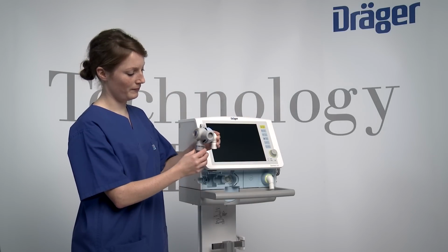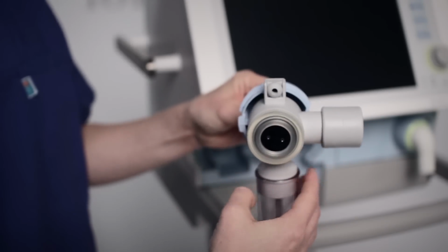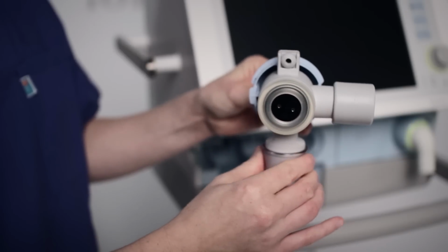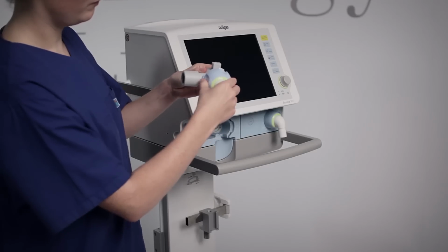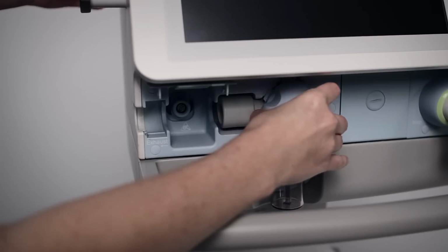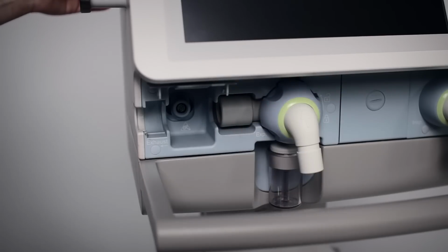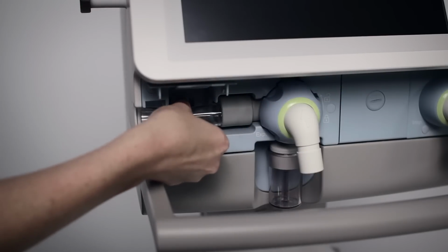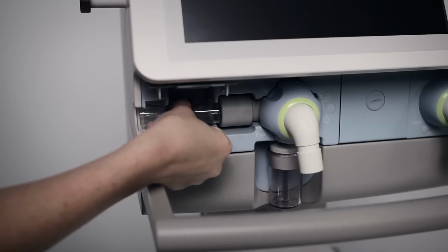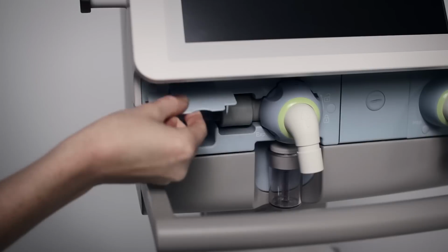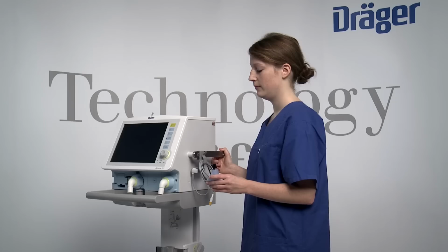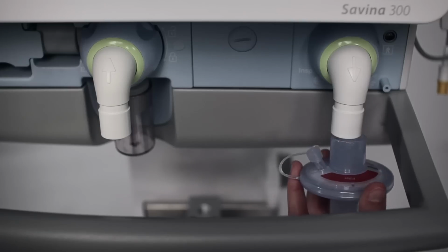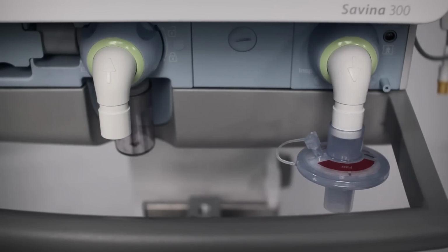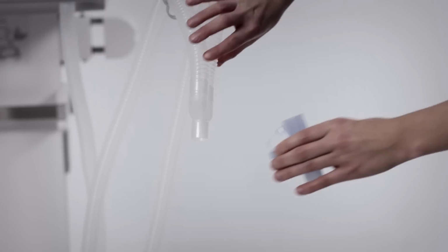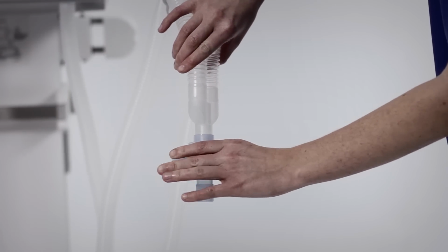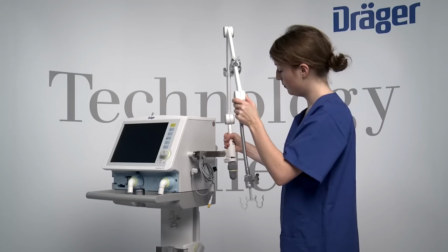Prepare the expiratory valve. Check that the diaphragm fits properly onto the edge of the expiratory valve housing, and that the flow sensor sleeve and the water trap container have been attached. Then insert the expiratory valve. After that, insert the flow sensor and push it up to the stop in the flow sensor sleeve of the expiratory valve. If no breathing gas humidifier is used, we recommend the use of an inspiratory bacterial filter, which has to be fitted onto the inspiratory port, or an HME which you can put onto the Y-piece.